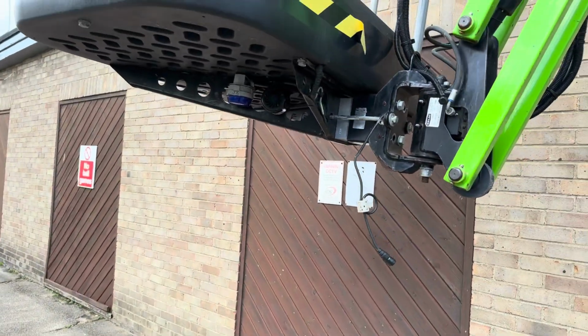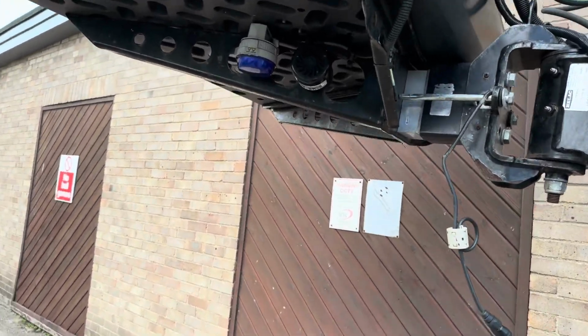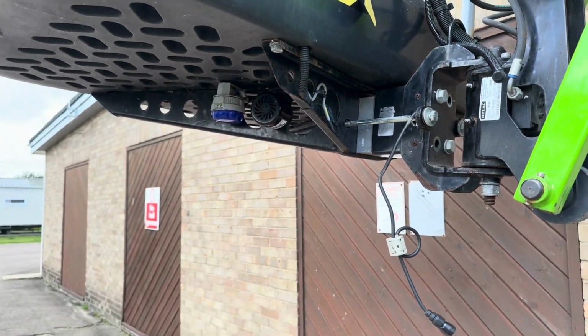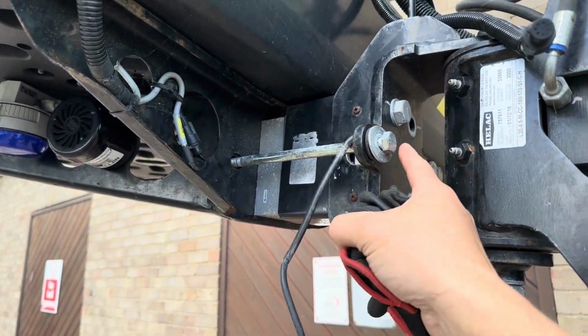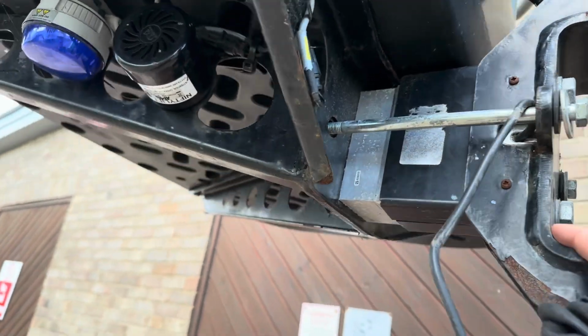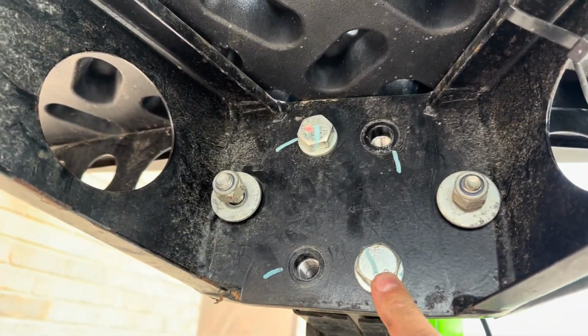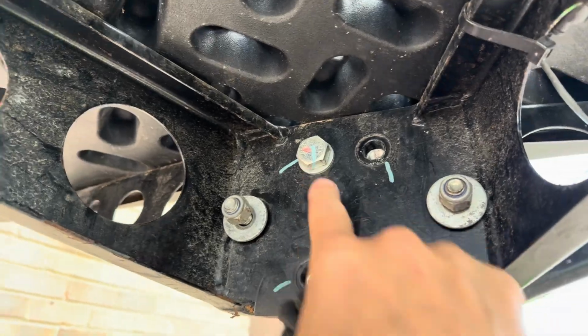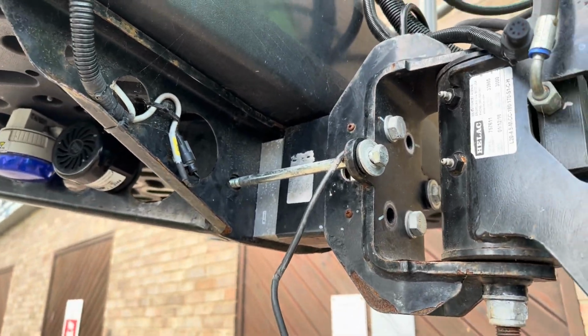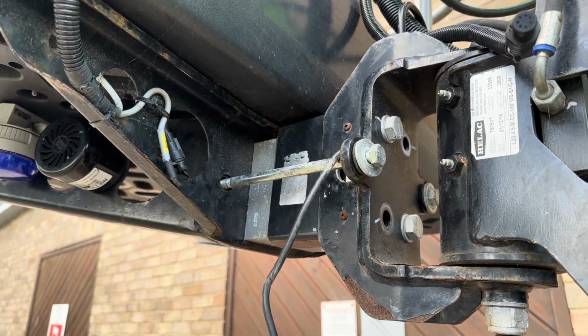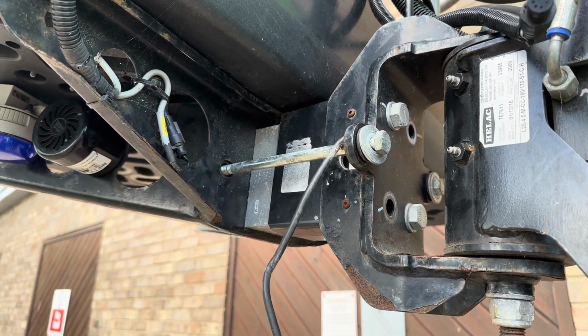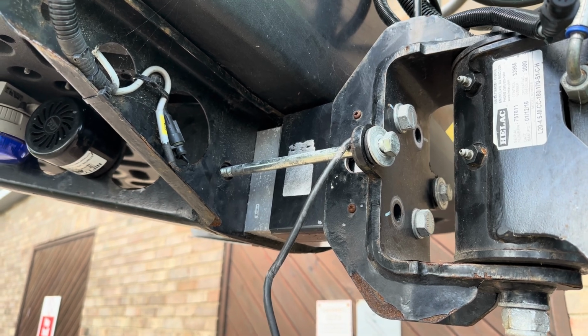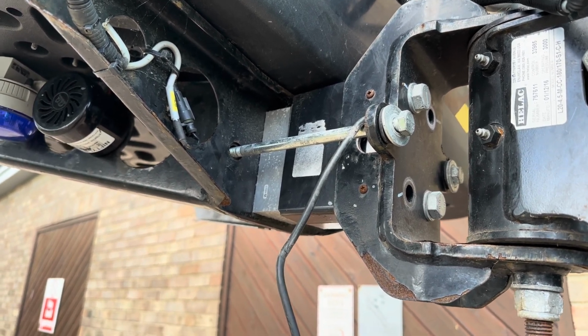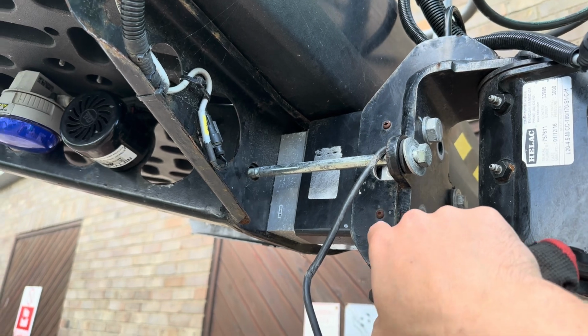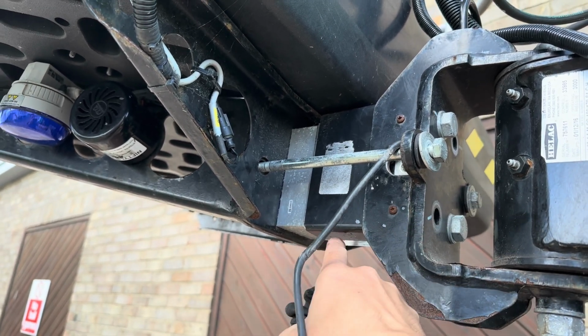So I'm in the process of the load cell change. The way I do it is I lift it all up so I have good access to the bolts. I will remove 2 bolts from this side and 2 bolts from this side, and I loosened up those 2. So the floor is kind of loose, and I will try to lower it down on the floor now, and then I will be able to remove the cell without too much trouble. And I just need to remember to undo these post screws to release the plastic.